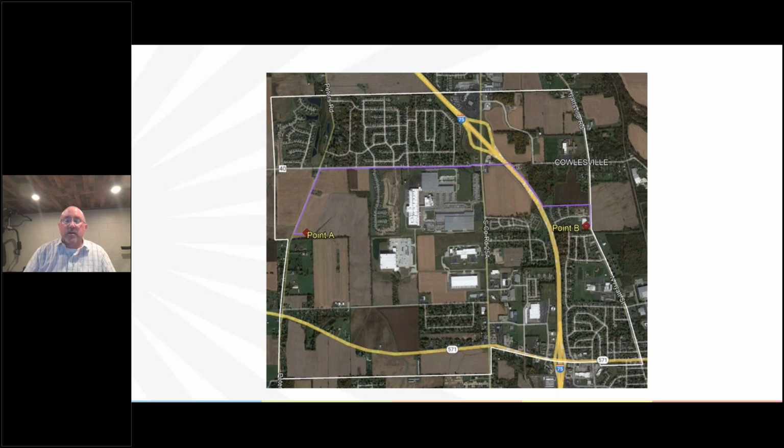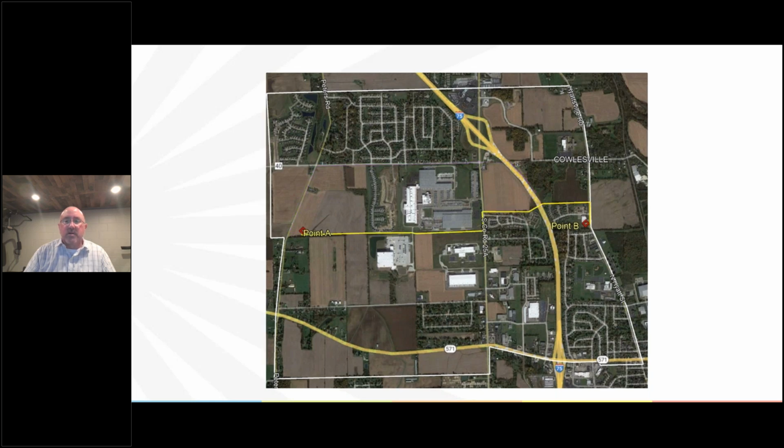We also selected the purple route to be an alternate to the preferred routes in case the preferred routes were unable to be constructed. It does go through a wetland and a park, but was shorter and less costly to construct than the eliminated alternative route that went further north. We spoke with the client about the route to ensure they would be willing to deal with the pushback and possible wetland permitting, and they were fine with that.